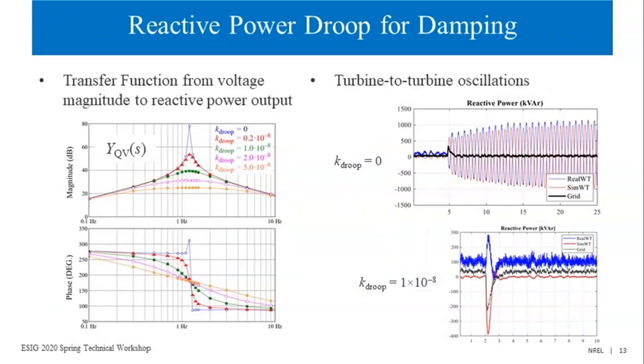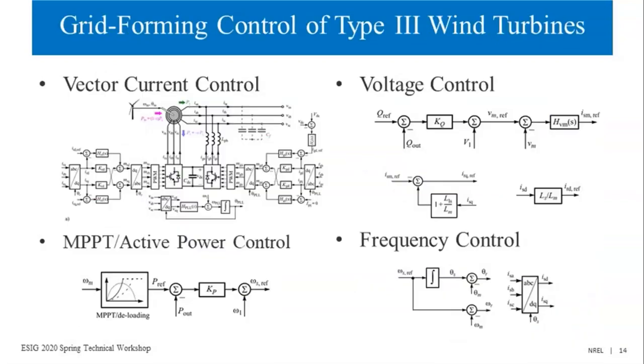Here they are damped by introducing a droop control between reactive power and voltage. By measuring this power domain impedance, or basically the transfer function from voltage magnitude to reactive power, we can clearly see that this droop is eliminating that resonant mode. And that is what I think happened in the Hornsea wind plant: there was a resonant mode inside the wind turbines, which went unnoticed, but created these reactive power oscillations.